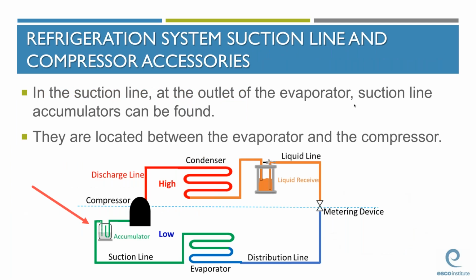In addition to the high side system components such as filter dryers, sight glasses, and receivers, your students will also need to know about low side system accessories such as the accumulator. The suction line accumulator is located at the outlet of the evaporator, and it prevents liquid refrigerant from flowing into the compressor. One thing I really like to do in class, when I'm discussing the accumulator with my students, is reference the refrigerant receiver in the same discussion. The accumulator is on the low pressure gas line, while the receiver is on the high pressure liquid line. The receiver is used to ensure that 100% liquid enters the metering device, while the accumulator ensures that 100% vapor enters the compressor. So the accumulator and the receiver are pretty much polar opposites of each other. And I use that analogy there to help the students understand the concepts and how these two components work.